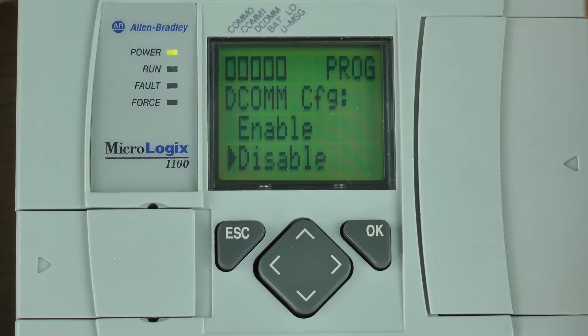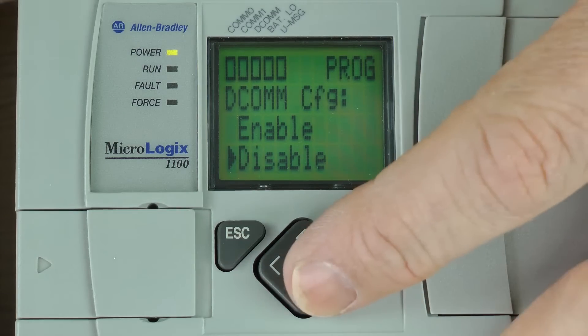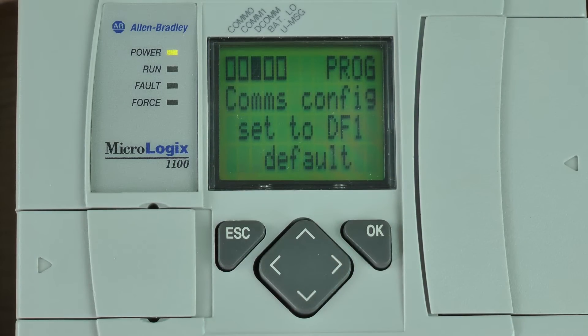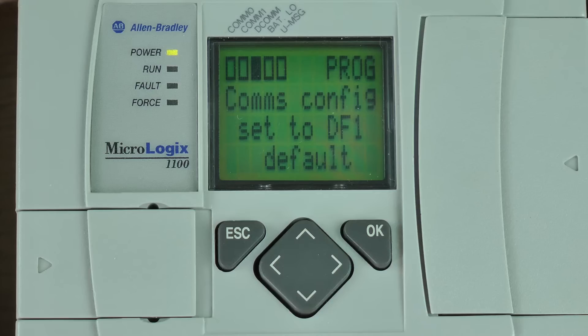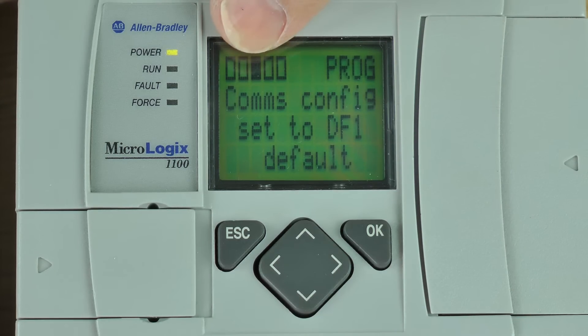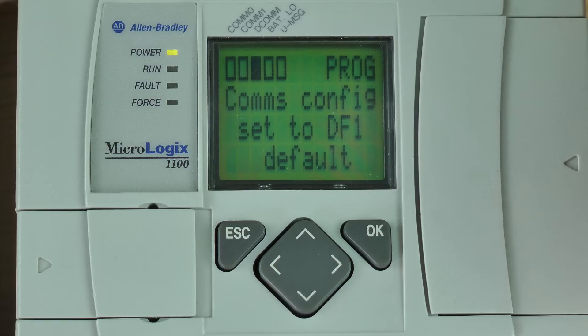So now I'm going to enable the DCOM. I'm going to press the up arrow key once, then press okay. You can see I immediately get a message that says comms config set to DF1 default. I also see the middle square at the top of the screen is now solid indicating that DCOM config is enabled.